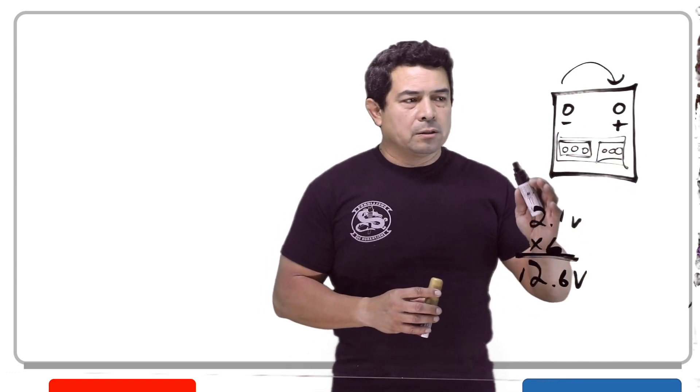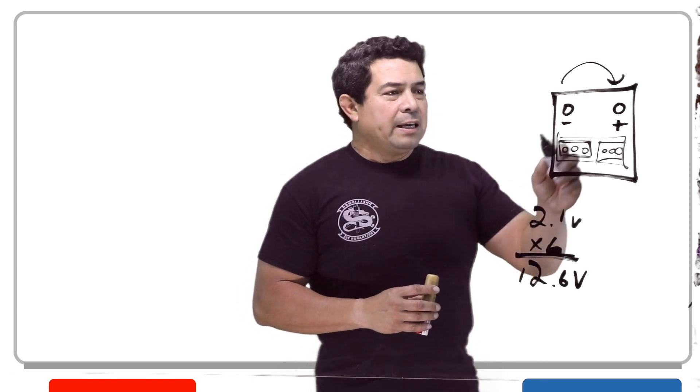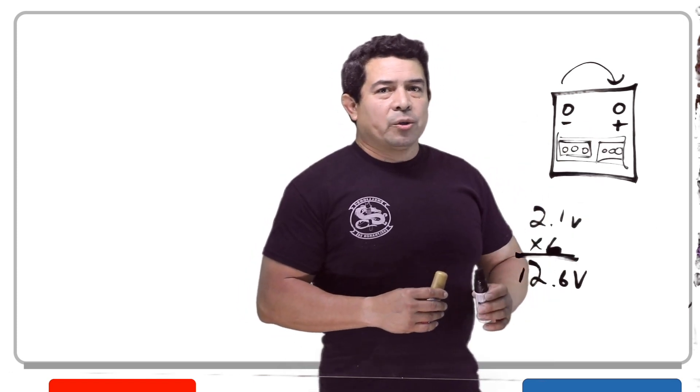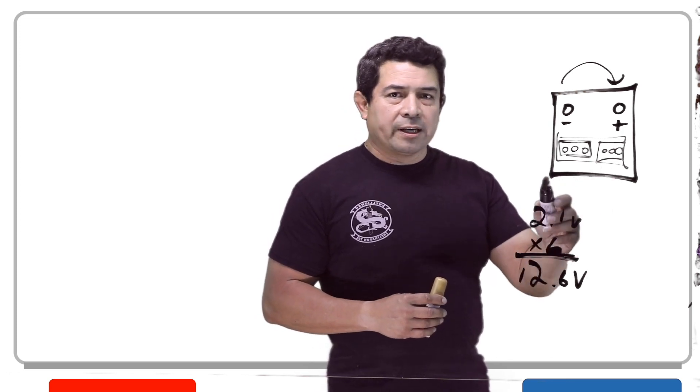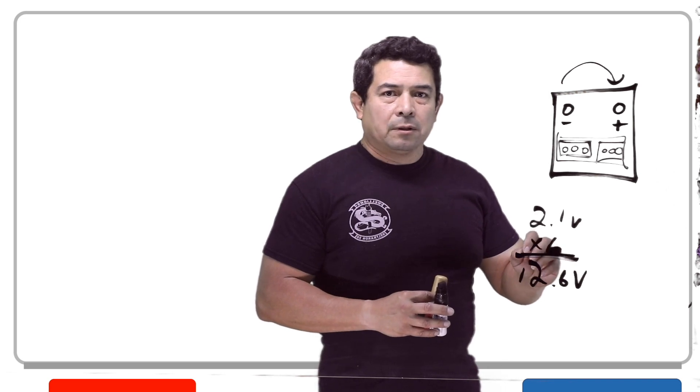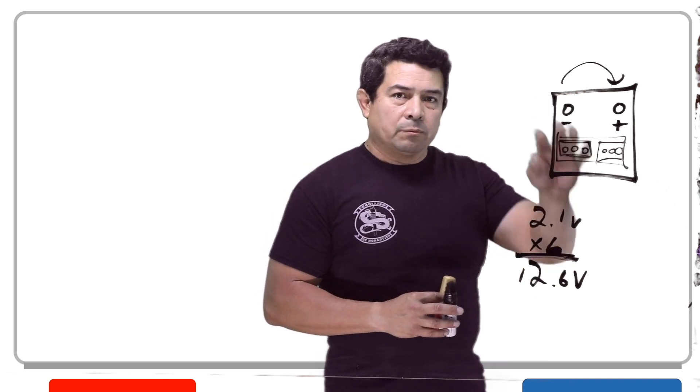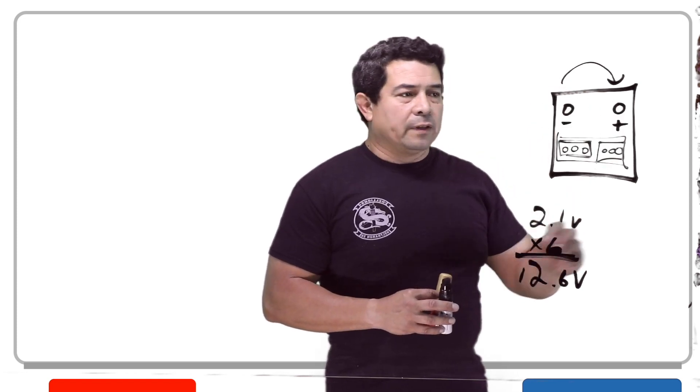What I'm trying to tell you is that that mixture of baking soda and water, you don't want it going into the battery. So don't take the plugs out, leave them in there. You take that mixture, put it on the battery, and you scrub it real well. Make sure that you get it everywhere and you wash it off, and then you pour water on it and rinse it all out.